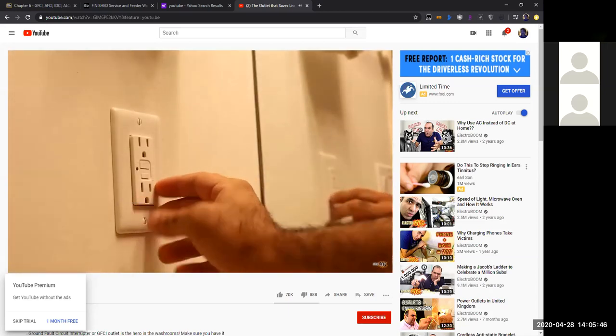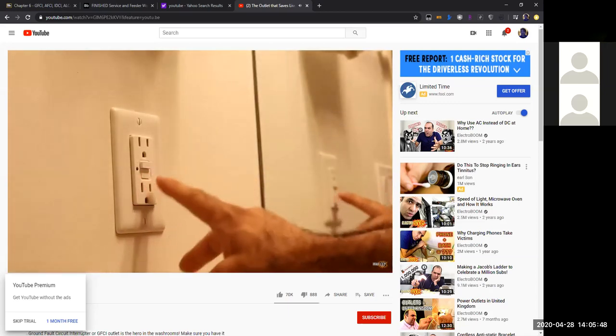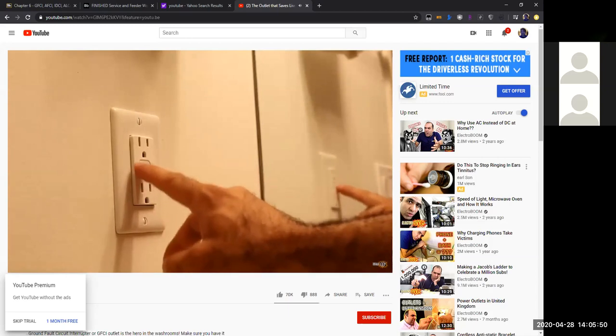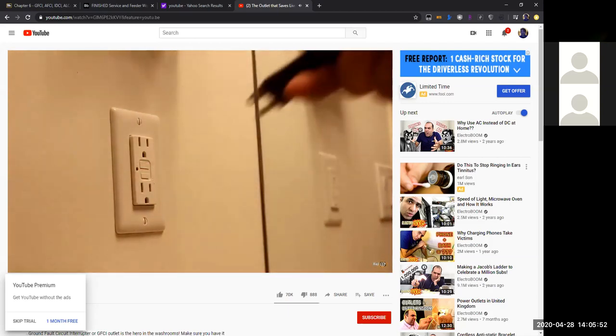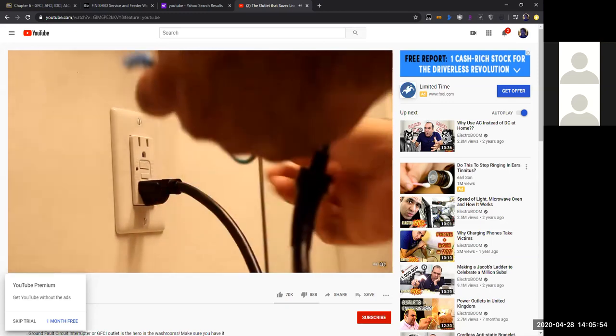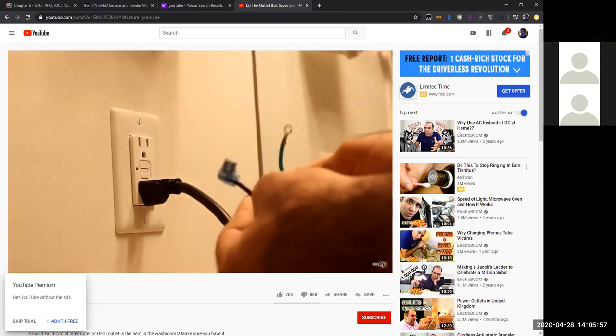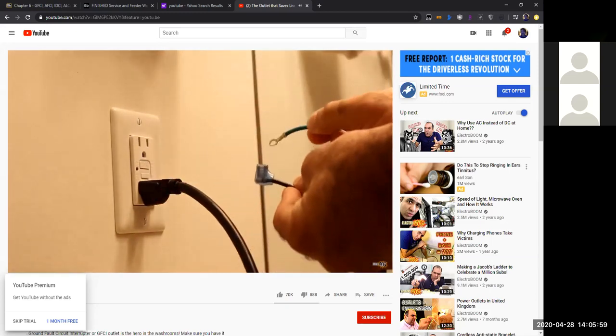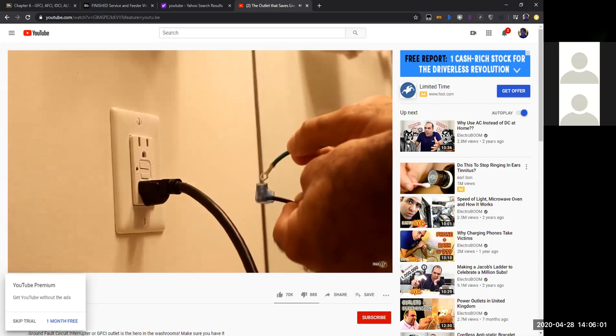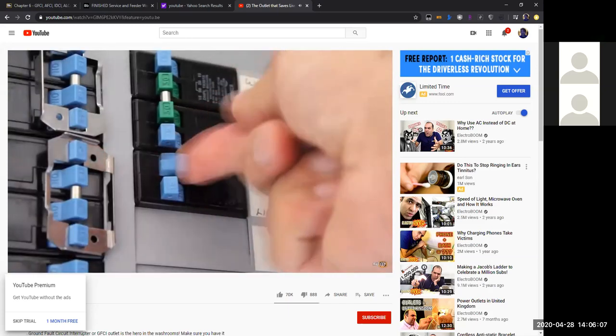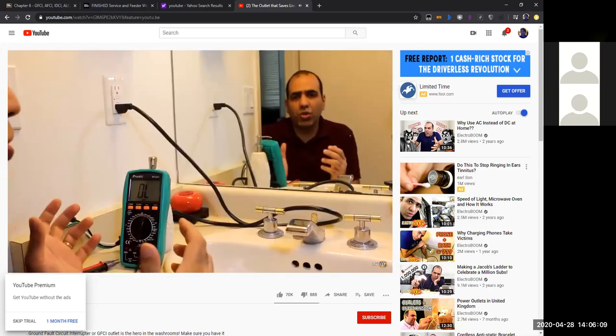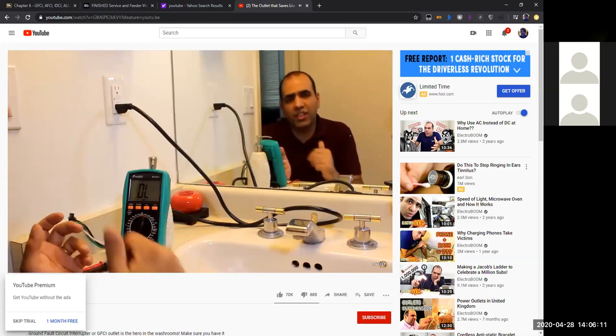Okay, let's test it out. It says test monthly, there's a test button, okay? And the red light is off, so it's all good. Now, if I plug in my wire and short the live, which is the black wire, to earth, which is the green, the breaker should pop. That wasn't the outlet breaker, the whole washroom breaker popped. Okay then, if it's a dead short, the room breaker opens quicker than the GFCI.